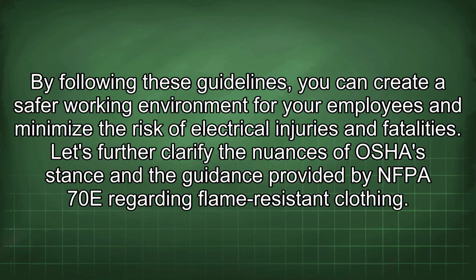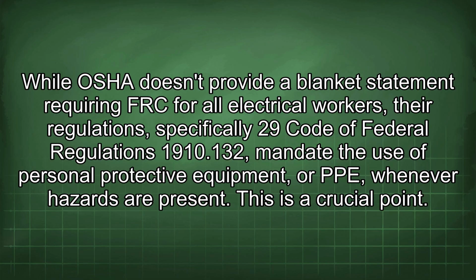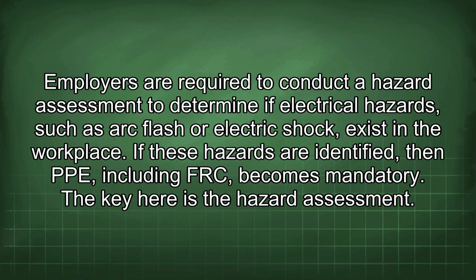injuries and fatalities. Let's further clarify the nuances of OSHA's stance and the guidance provided by NFPA 70E regarding flame-resistant clothing. While OSHA doesn't provide a blanket statement requiring FRC for all electrical workers, their regulations, specifically 29 Code of Federal Regulations 1910.132, mandate the use of personal protective equipment, or PPE, whenever hazards are present. This is a crucial point. Employers are required to conduct a hazard assessment to determine if electrical hazards, such as arc flash or electric shock, exist in the workplace.